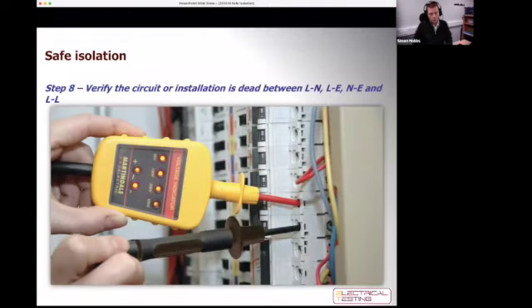Having now isolated and secured my isolation, I can now carry out my proving of the installation. So I will take my test lamp and ideally, certainly with a single phase installation, connecting to either earth or neutral first, so that I don't have a wandering live lead potentially. I'll then test between all conductors. So as on the slide here, typically we would be going something like line to neutral, line to earth, neutral to earth. And then if I've got a 3-phase installation, I would then be going between all of the line conductors, line 1 to line 2, line 1 to line 3, and so on.